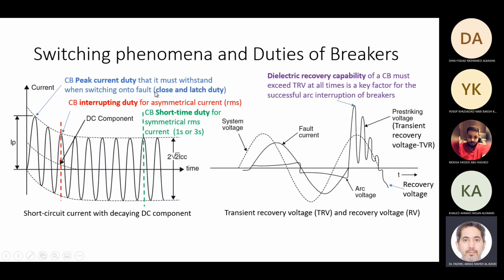So how does the breaker switch current? You can switch a breaker when there is already a fault. Before you switch a breaker, you have a short circuit already, so you switch on to a fault, or you have a fault while the breaker is closed, a fault occurs, then the breaker should open on that fault. So you have these two scenarios. When a fault occurs, the current has a decaying DC with it, as I explained before. The current goes to peak, and then decays, depending on the time constant of the decaying DC, until it reaches steady state.